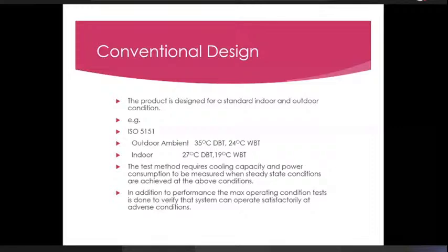So a test is performed where this unit is run under those conditions for 2 hours. And having run it for 2 hours, then the unit is switched off. It's kept off for 3 minutes. That is to give the compressor requisite time to have pressure equalization, and switched on. So it needs to get switched on, and it should not trip. So that becomes a reliability test.